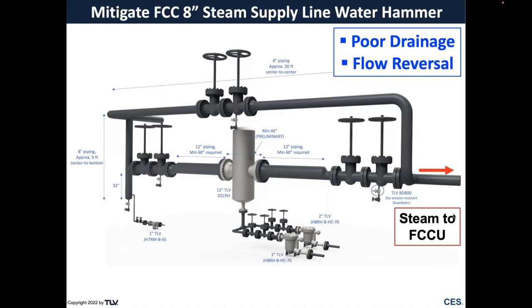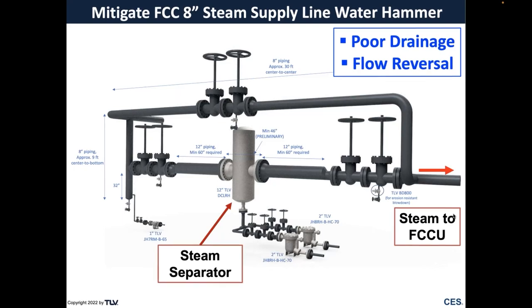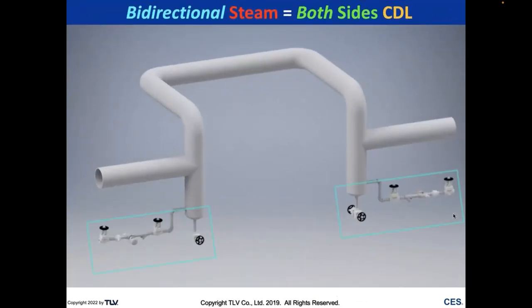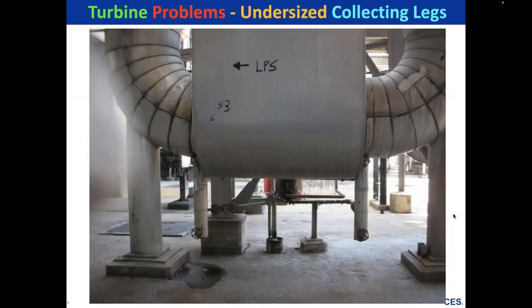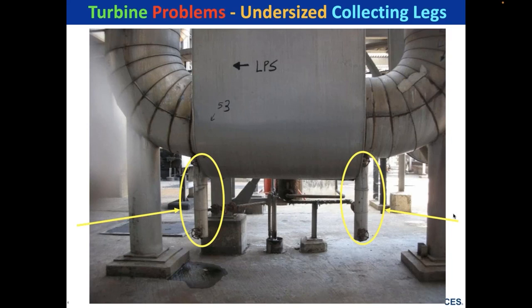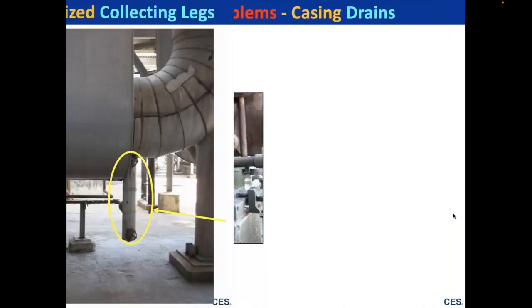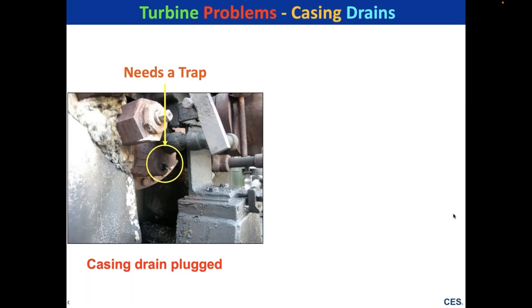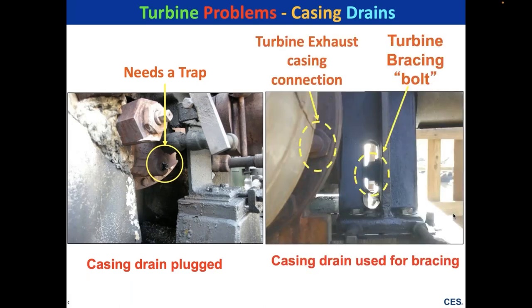To help the site, we did multiple things including condensate collection bottles. We put a steam separator finally before the turbines and the steam leading into the FCC unit. We don't want to damage that separator with slugs, so we address slugs beforehand with a condensate collection bottle and appropriate drain locations. For bidirectional flow, we put CDLs on both sides. Drain points on turbines are often inadequate — too small in diameter — and casing drains can be plugged.